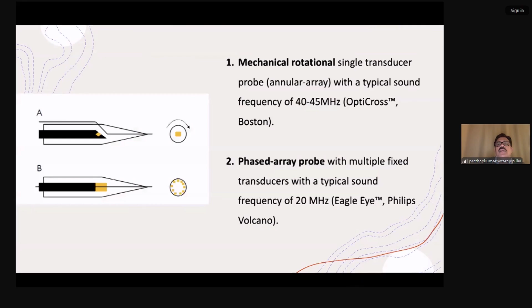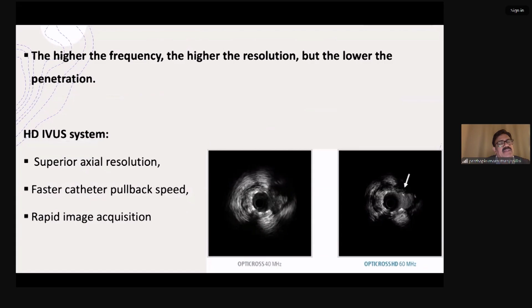You have a mechanical rotational single transducer probe as well as phased array probes available. The higher the frequency, the higher the resolution, but the lower the penetration. HD IVUS has superior axial resolution, faster catheter pullback, and rapid image acquisition. I personally use, we have the Philips Volcano catheter as well as this one, but the catheter which I like more is Boston Scientific. Basically, it's a 15 to 20 micron axial resolution. The advantage is actually a clear interface between the lumen and the plaque surface.